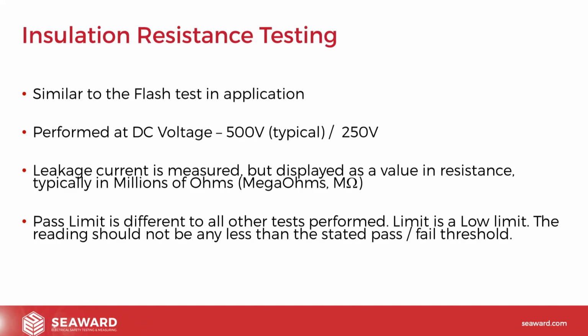As the name suggests, the insulation resistance test is a measurement of the quality of the insulation by means of a resistance test. The method of performing the test, in terms of connections to the device under test and the use of probes, is identical to that of the flash test. So everything you're familiar with in the hire industry in terms of how you make connections, which probes you use, and where you place the probe is effectively identical between a flash test and an insulation resistance test. The main difference with this test is the voltage is lower. We're typically performing it at DC voltage. 500 volts is the more common test in order to stress the insulation under fault conditions.